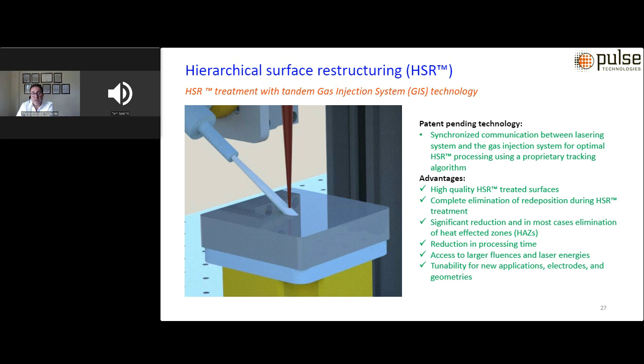As an example, you can see the difference between electrodes that are restructured with a gas injection system and without. There are, again, a number of benefits to doing this. For example, we've received feedback from some customers that there is some dissolution of the electrode in certain cases under extreme pulsing conditions, and we've been able to work with this tandem gas injection system technology to reduce the amount of redeposition and recast on the surface of the electrode after restructuring, which makes it really interesting and unique in many ways.